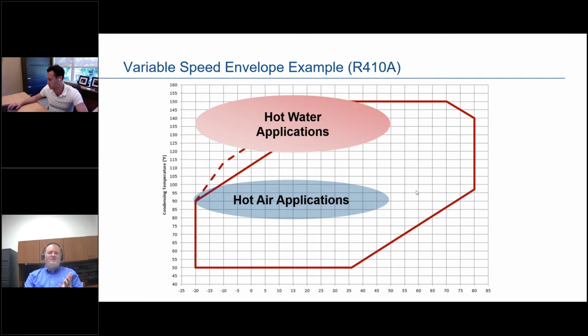And then, a lot of these applications may be dual purpose. Some may be just making hot water, some may be making chilled water and hot water depending on the season, or chilled water and hot air. So variable speed gives you more flexibility, with one compressor that can optimize for cooling and for heating design based on whatever loads the system requires.